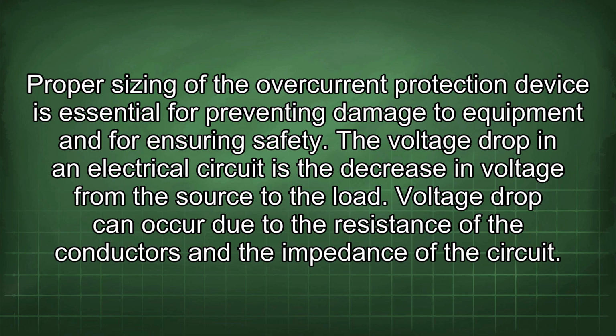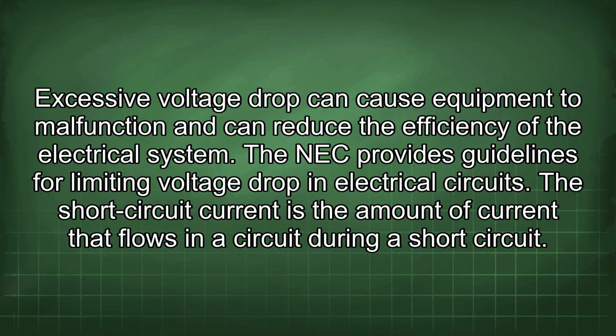The voltage drop in an electrical circuit is the decrease in voltage from the source to the load. Voltage drop can occur due to the resistance of the conductors and the impedance of the circuit. Excessive voltage drop can cause equipment to malfunction and can reduce the efficiency of the electrical system. The NEC provides guidelines for limiting voltage drop in electrical circuits.